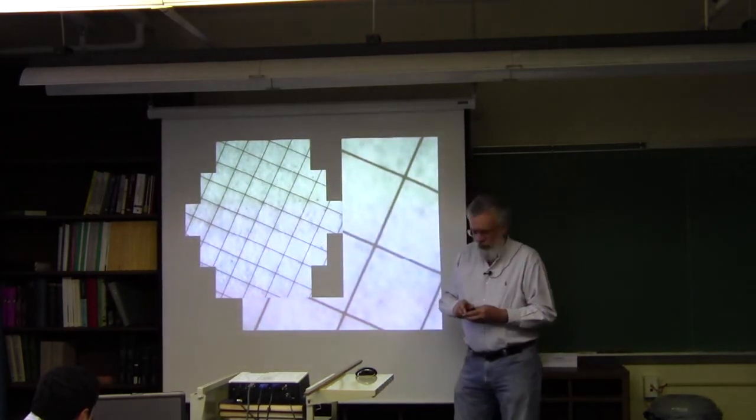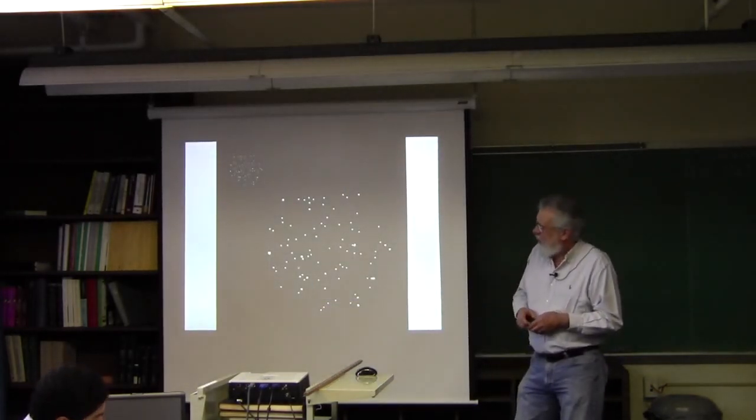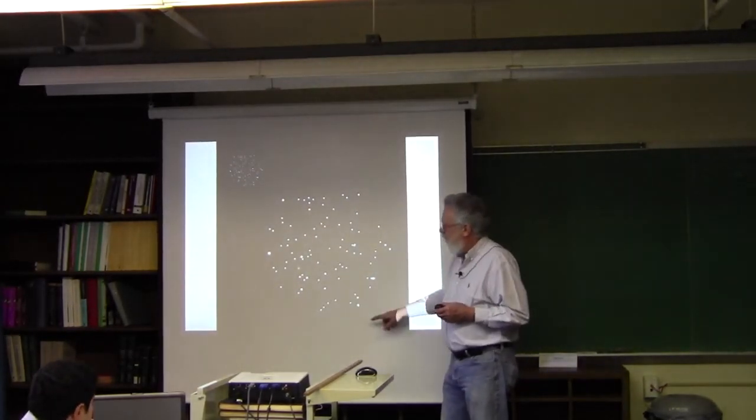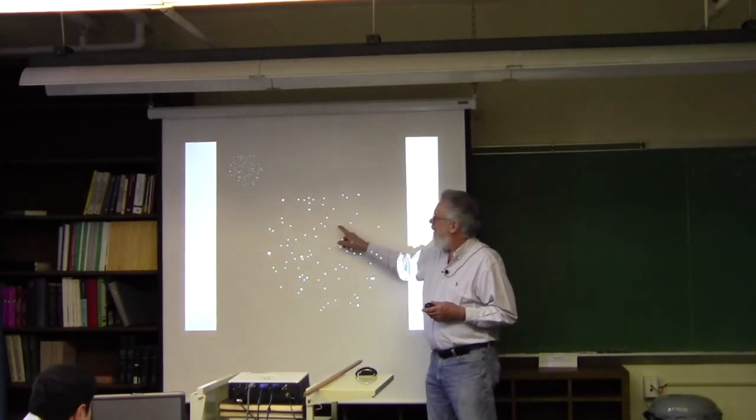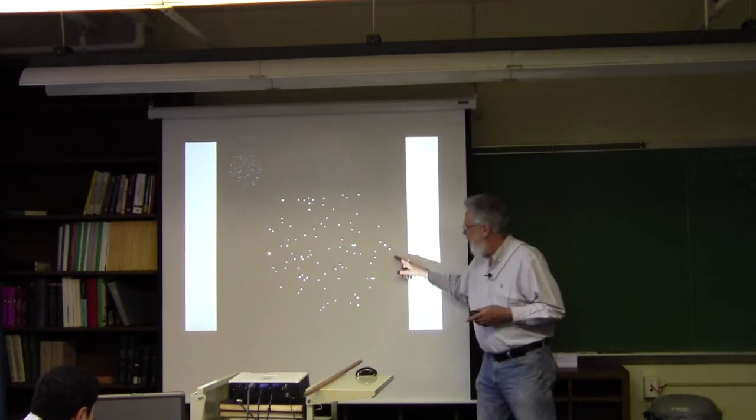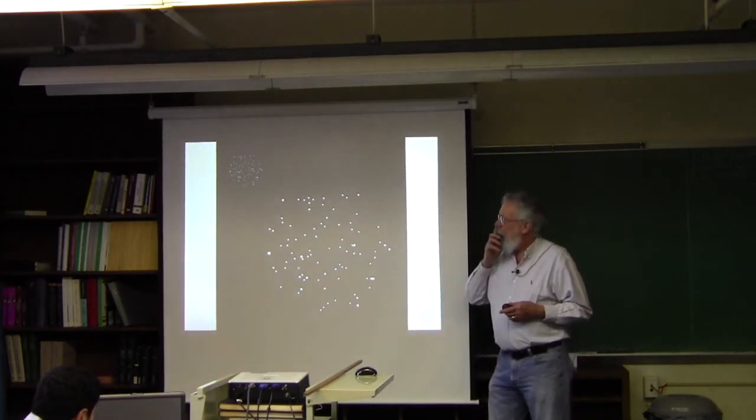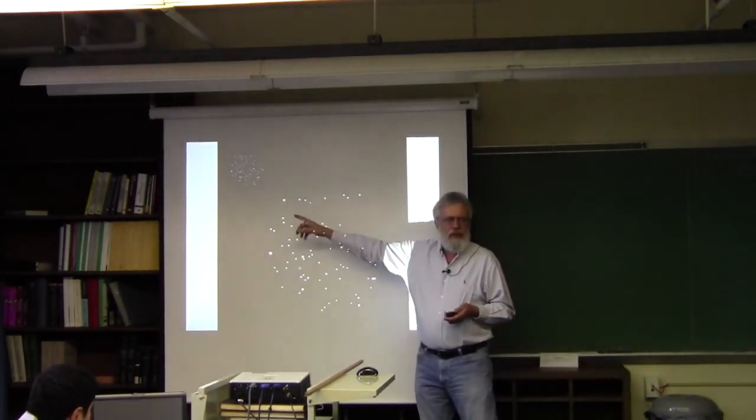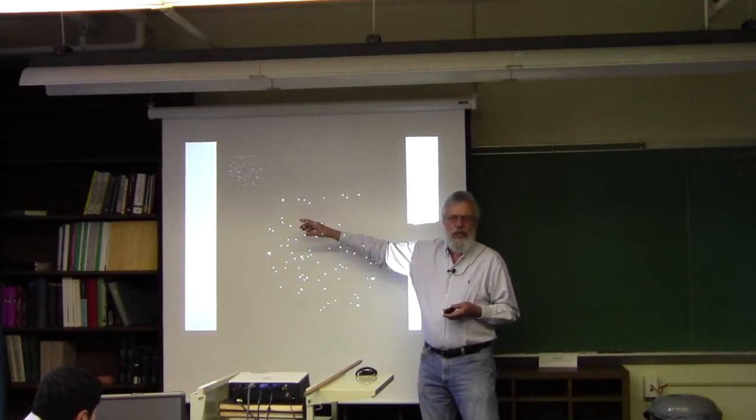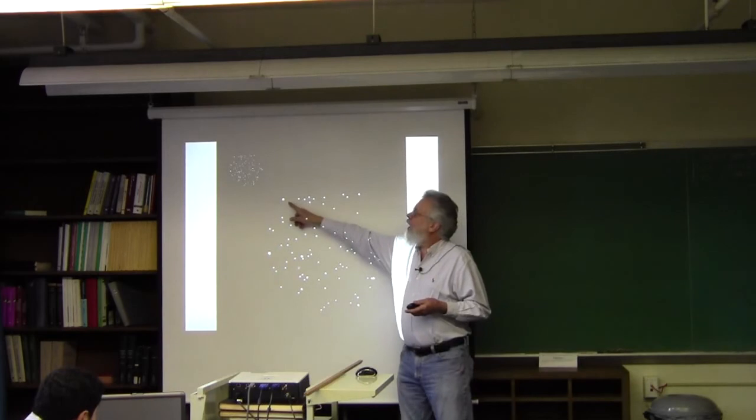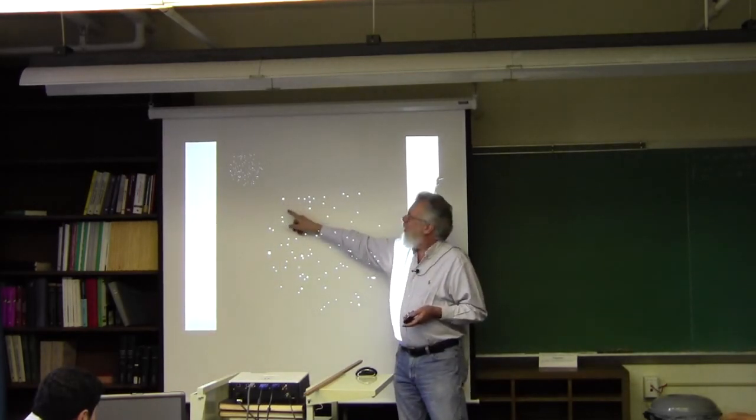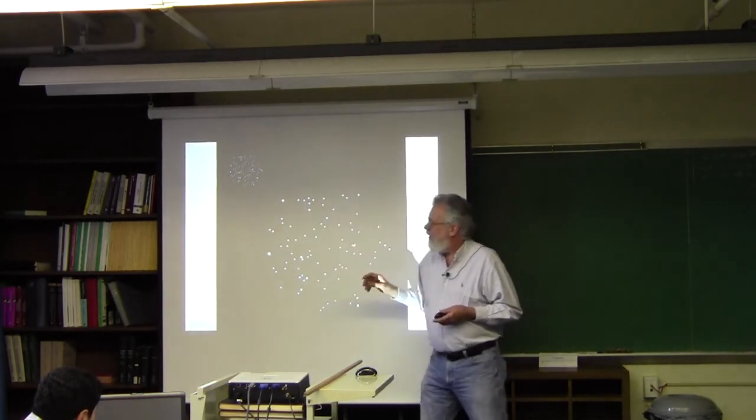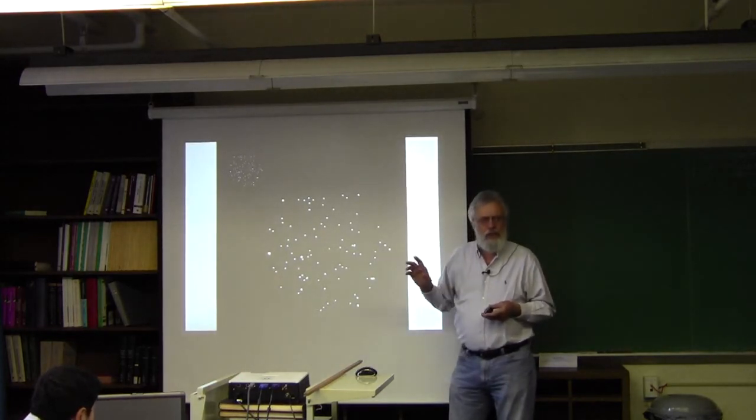That's an image of a scan. This is a dish, six millimeter diameter. These are individual cells or maybe beads, I can't tell which. We know where these are. If we were going to scan this area with a high magnification lens we would be taking lots of pictures of empty space. This is the reason for our initial scan, so we know which high magnification frame would contain this cell and we would know that there's no reason to go here because there's nothing there. The initial scan tells us where to go with the high magnification lens to find things that are interesting to shoot.